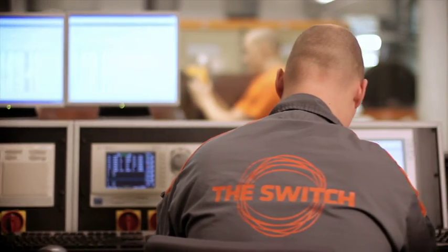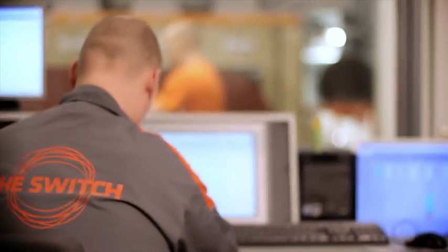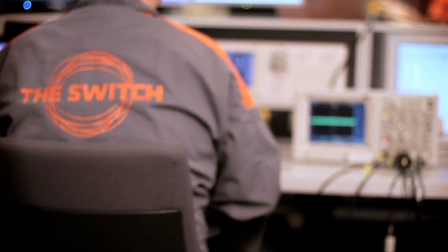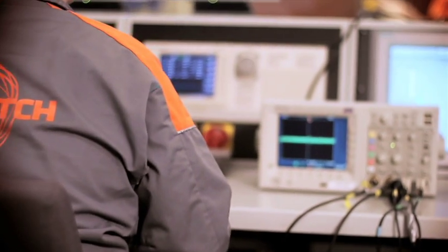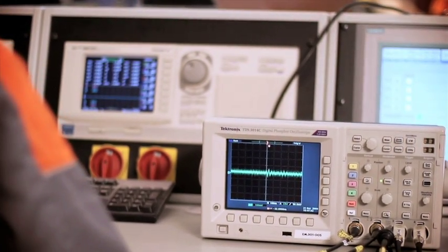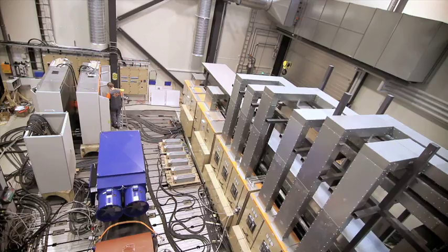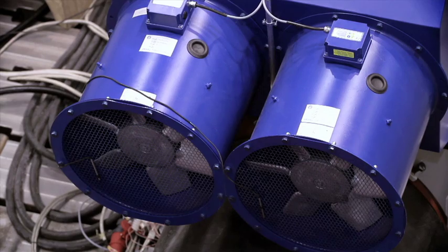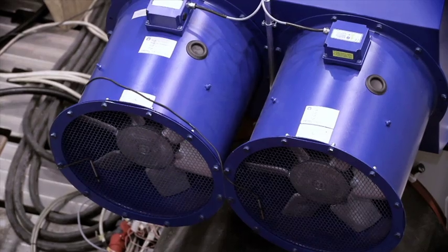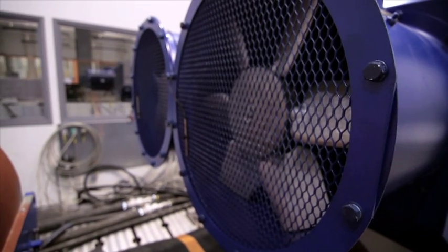Switch type testing is more detailed compared to the routine testing carried out for every generator, because we need more detailed information about the generator to find out its performance. We have very accurate measurement equipment tailored for this type of testing. What's special about this Lappeenranta factory test field is that we can simulate the conditions of a wind turbine nacelle, including the ambient and coolant temperatures and similar factors.